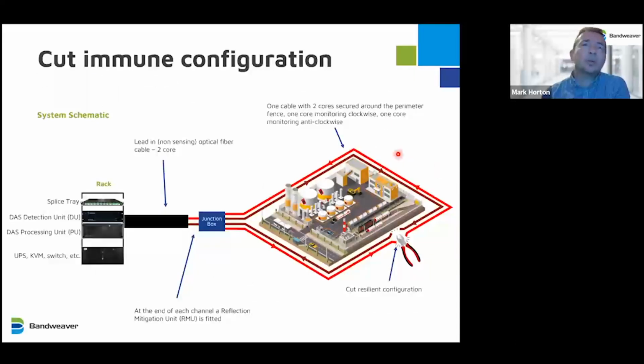And the reason we use 2 cores, so here's the rack coming out to the junction box. And we have 1 core, which is effectively monitoring in a clockwise direction, and 1 core monitoring in an anti-clockwise direction. Again, just one cable, but with two cores. And the reason being is if someone cuts the cable, cutting through both cores, the system still monitors up to the point of cut. So this core is still monitoring up to the point of cut in this direction, and this core in this direction. So you pretty much retain 100% detection.